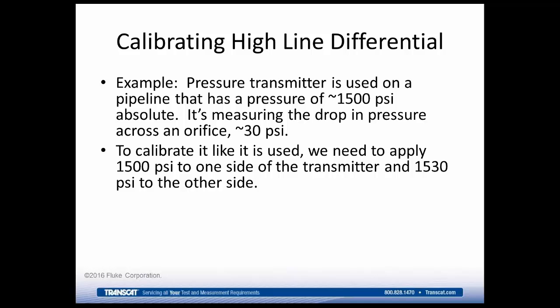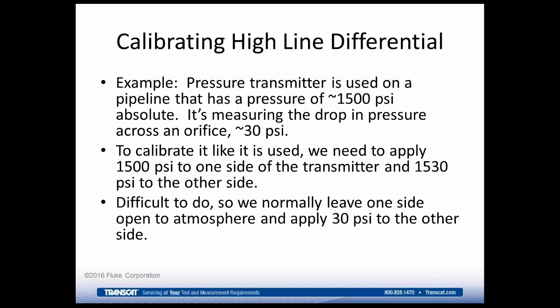Generally speaking, it's always best to calibrate a device as similar to how it's used in the real world as possible. So that way your calibration adequately covers the potential errors that the device has in its normal application. If we're going to do that in this case, then we need to apply 1500 psi absolute to one side of the transmitter, and 1530 psi absolute to the other side. That's difficult to do and to measure correctly. We could have two absolute mode standards of say 2000 psi absolute full scale, and we apply those pressures and read them off of there, but our overall error in terms of the differential will be quite high. So that's difficult to do.